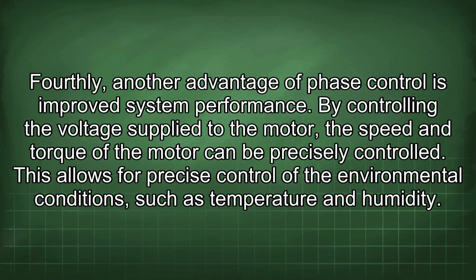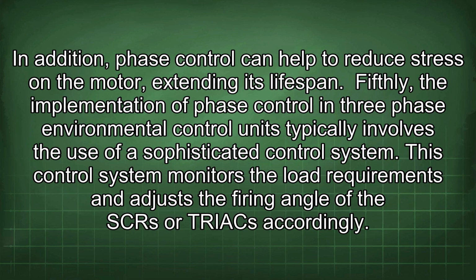Fourthly, another advantage of phase control is improved system performance. By controlling the voltage supplied to the motor, the speed and torque of the motor can be precisely controlled. This allows for precise control of the environmental conditions, such as temperature and humidity. In addition, phase control can help to reduce stress on the motor, extending its lifespan.